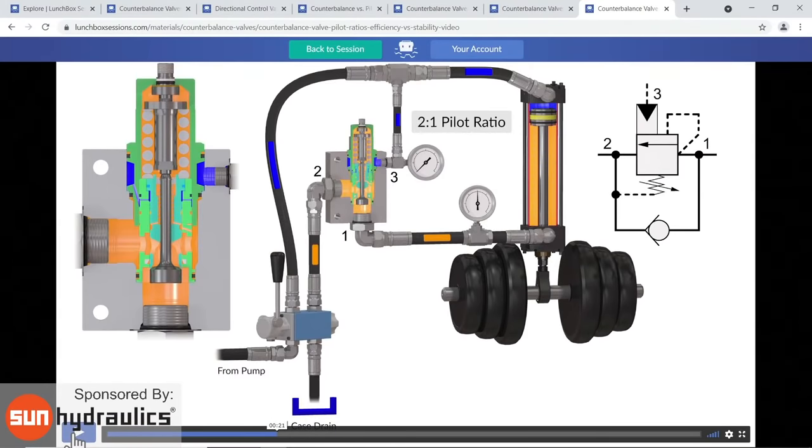Then we get to the top, and this is us now with our float center directional valve, and it's been centered. Now we're just hanging on to our weightlifting equipment here. That's our mass, some dumbbells. Our annular side of the hydraulic cylinder piston is keeping a volume of oil compressed against the closed poppet, which I think you now understand, the poppet arrow 1 to 2 and the backside of the check valve function in the symbol are really the same point of closure. So there is our load-induced pressure, our static hold pressure, and there's really nothing to see here.